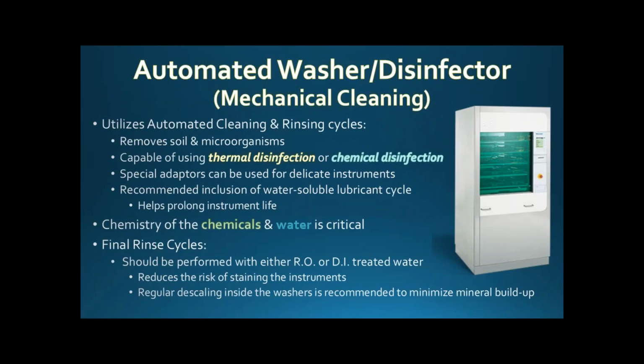After that, most of our sterile processing departments now have an automated washer disinfector. So after the instruments have gone through the sink and the ultrasonic, we put them in our washer disinfector. These are great. They remove organisms, they remove soil. They are capable of performing thermal disinfection or chemical disinfection. So when the instruments come out on the other side, they are safe to handle, right? Because they've been disinfected appropriately. They have special adapters, so if you're using robotics, you can attach these special adapters to help make sure they're getting into the lumens and all these different things. A lot of washers also use a water-soluble lubricant because that really helps prolong the life of your instrumentation.